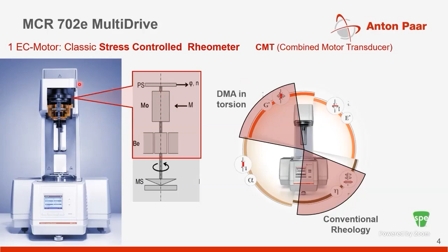This multi-drive device also comes ready with an option to put a rotational drive in the bottom chassis, which converts it into a separate motor transducer, or what some people call a strain controlled rheometer. Here there are two drive units, which can be employed in a synchronized fashion, where the lower drive applies the deflection and the upper drive remains stationary, acting like a torque transducer.